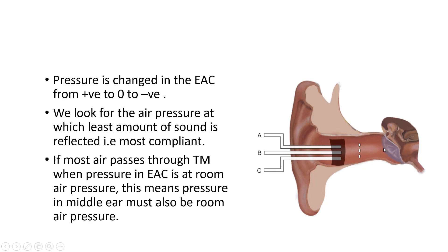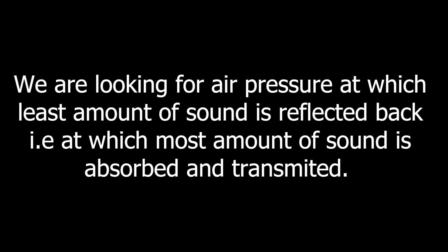When we further decrease the pressure from 0 to negative — creating a negative pressure in the external ear — the tympanic membrane again becomes stiff. It does not allow the sound waves to pass through to the middle and inner ear, and most of them are reflected back. Again the compliance is low and stiffness or resistance is high. We are looking for the air pressure at which the least amount of sound is reflected, or the most amount of sound is transmitted through the tympanic membrane to the middle and inner ear.